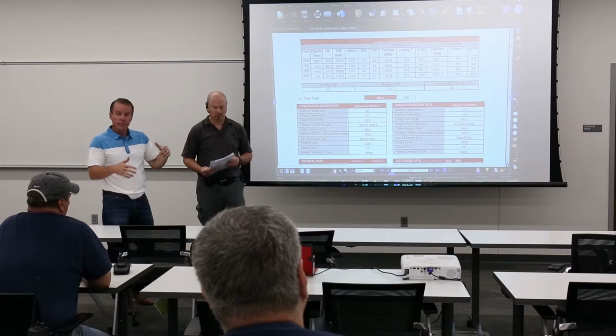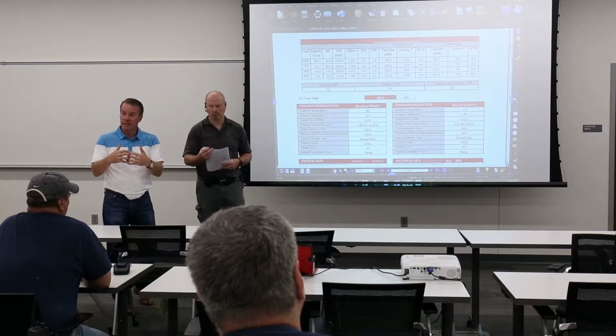So when you have campus chilled water available to the building, this chiller is a heater. Think of this chiller as a heat recovery machine anytime you have campus chilled water available. This chiller is going to produce 130 degree water off of its condenser, and that 130 degree water is to be used for the heating loop in the summertime. The heating loop is there so that you don't have to run a boiler. You're going to run the chiller, it's going to give you 130 degree water, and the byproduct of the chiller is then going to be cooling.